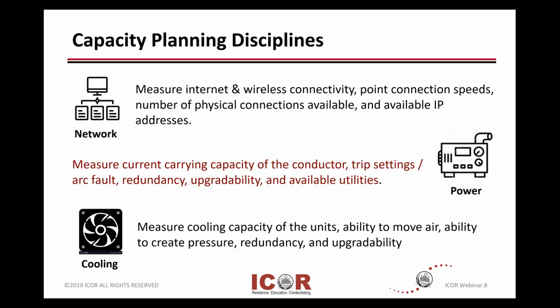And it's not only capacity, but also distribution capability. Can I get the cooling and power where I need it? Or have I created block zones, whether through ramps, zoning, demising, or obstructions? And the ability to move the air as desired, and to create pressure redundancy and upgradability.